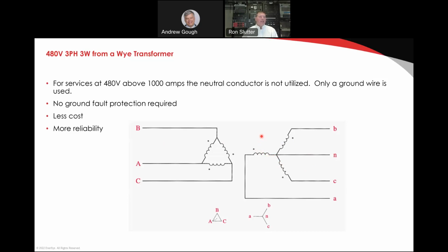If you did need lighting at 277 volt, which you can obviously get around as well by using 120 volt lighting, you could put in a small transformer to derive a neutral and eliminate hundreds of thousands of dollars worth of main service cost, just to pick up a small transformer to do the lighting. So this is very important for you to recognize.